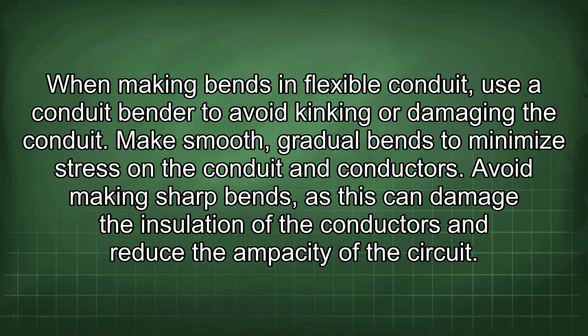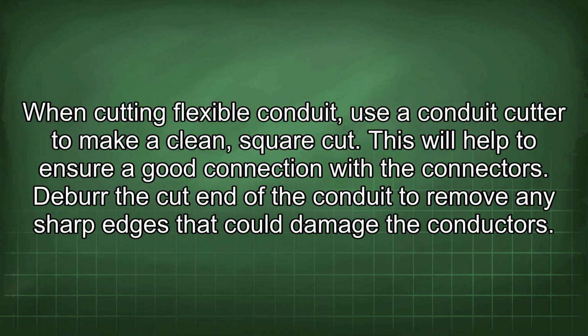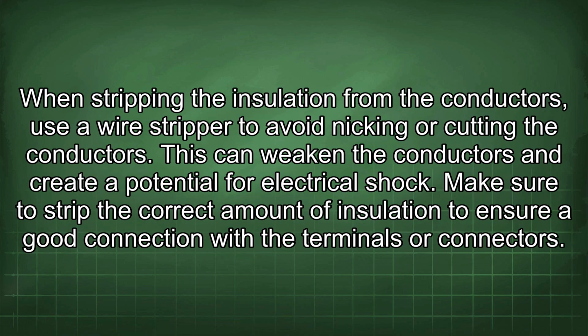Make smooth, gradual bends to minimize stress on the conduit and conductors. Avoid making sharp bends, as this can damage the insulation of the conductors and reduce the ampacity of the circuit. When cutting flexible conduit, use a conduit cutter to make a clean, square cut. This will help to ensure a good connection with the connectors. Deburr the cut end of the conduit to remove any sharp edges that could damage the conductors. When stripping the insulation from the conductors, use a wire stripper to avoid nicking or cutting the conductors. This can weaken the conductors and create a potential for electrical shock. Make sure to strip the correct amount of insulation to ensure a good connection with the terminals or connectors.